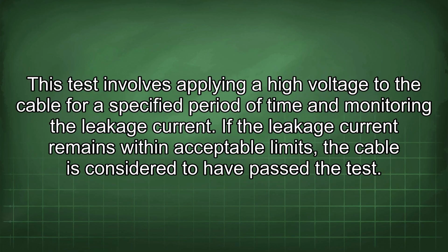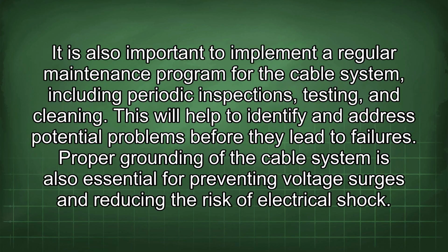This test involves applying a high voltage to the cable for a specified period of time and monitoring the leakage current. If the leakage current remains within acceptable limits, the cable is considered to have passed the test. It is also important to implement a regular maintenance program for the cable system, including periodic inspections, testing, and cleaning. This will help to identify and address potential problems before they lead to failures.